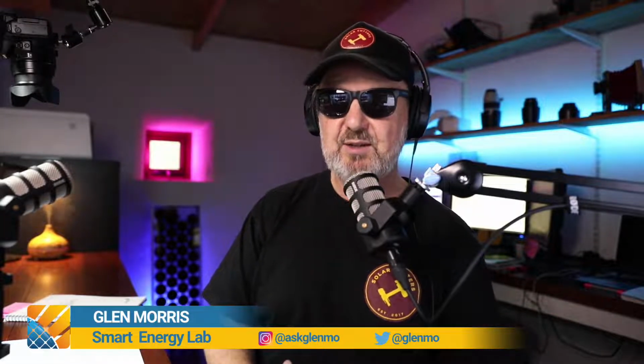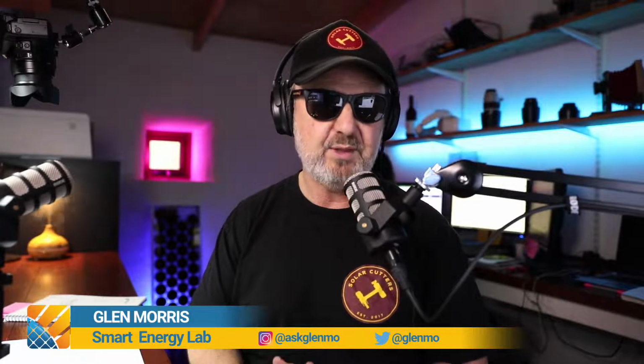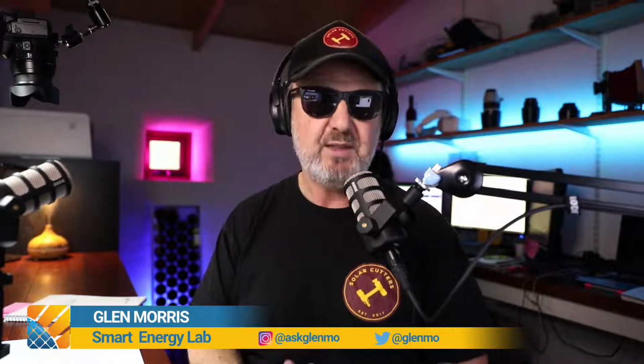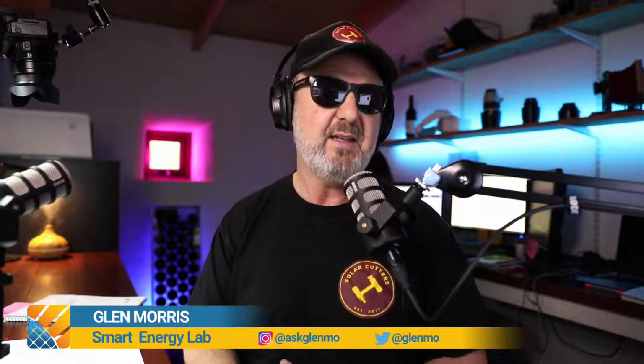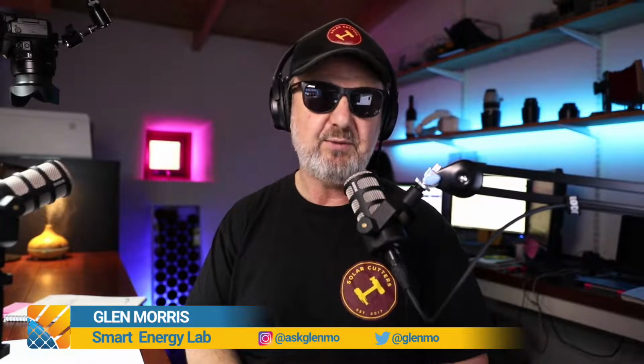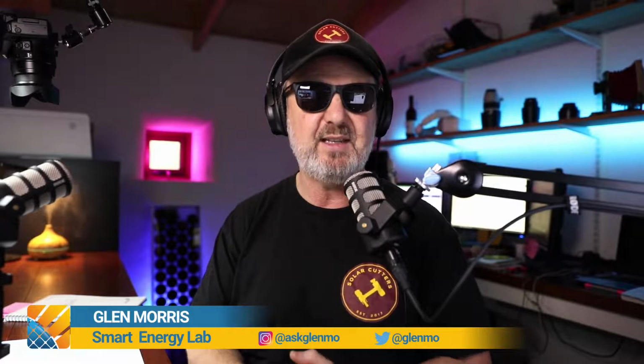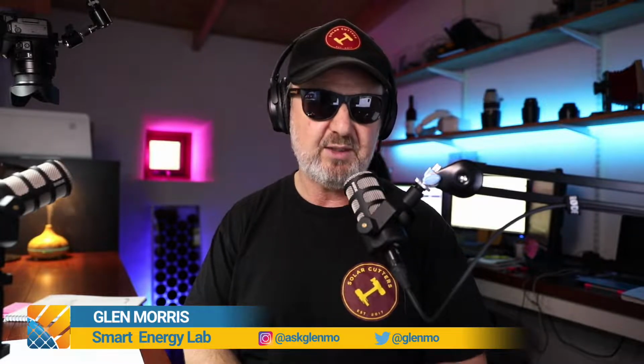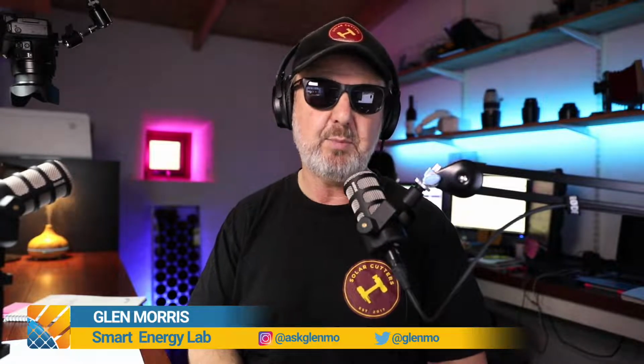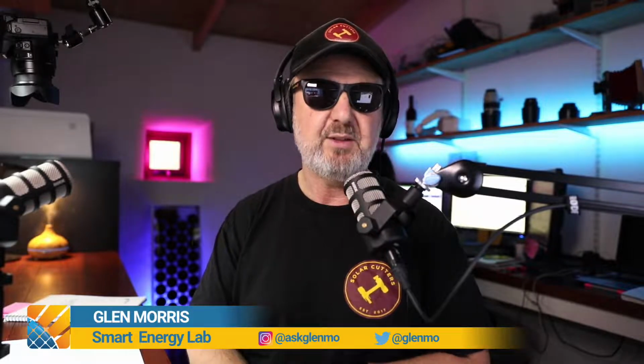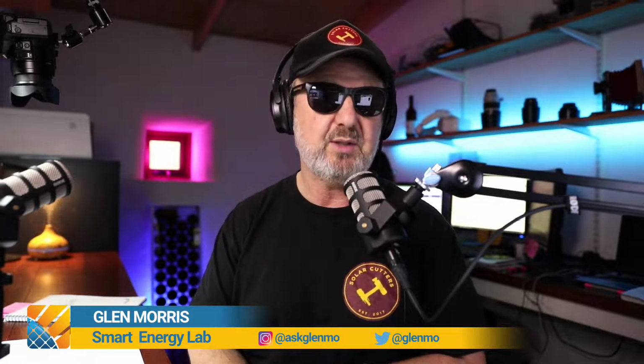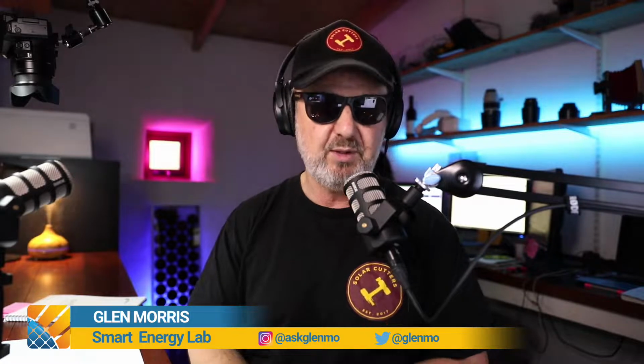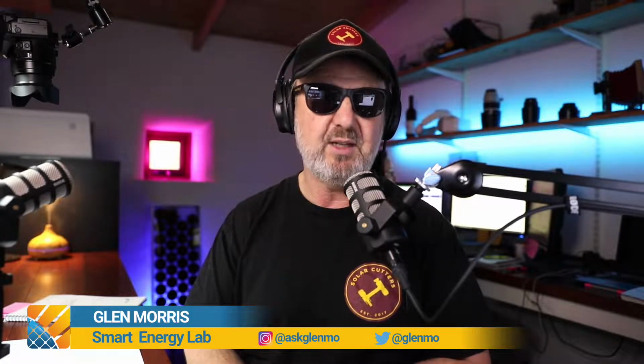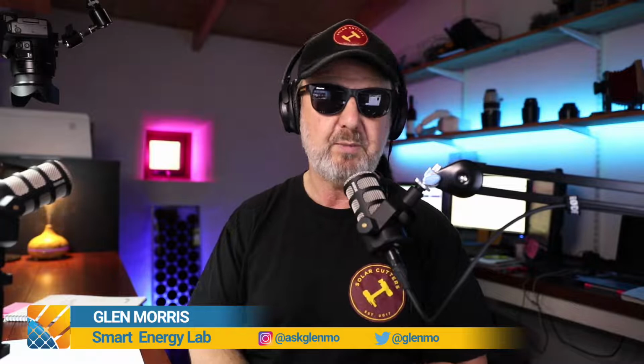Reaching out to those in New Zealand, because we have quite a few followers from New Zealand on my channel. In New Zealand, this is a kind of vague adoption because it's not yet referenced in the New Zealand electricity regs. It is really a best practice guide, but it has been pointed out to me by the New Zealand regulator that since it isn't replacing an existing standard and it is providing safety information, there is an argument that you do need to comply with it. So take that for what it's worth. It is actually a really good design document too, but some parts of it are a bit curly and a bit tricky.